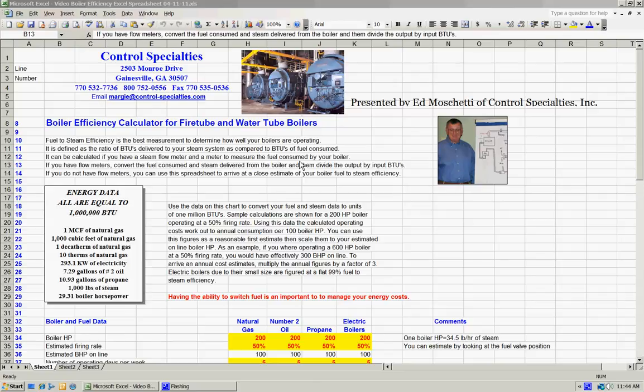Fuel to steam efficiency for a boiler is comparing mathematically the output of the boiler in BTUs compared to the fuel burned measured in BTUs. So for a boiler firing natural gas, we'd look at the amount of steam delivered to our facility, convert that to BTUs.